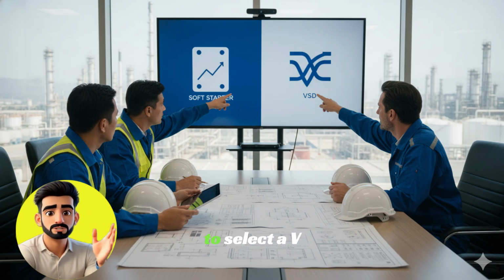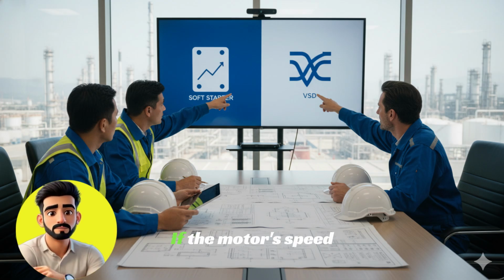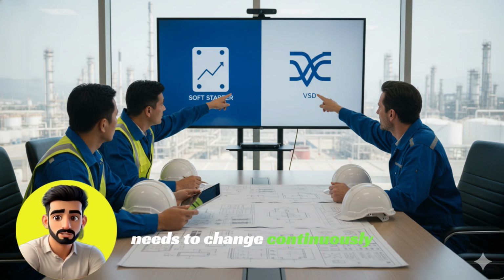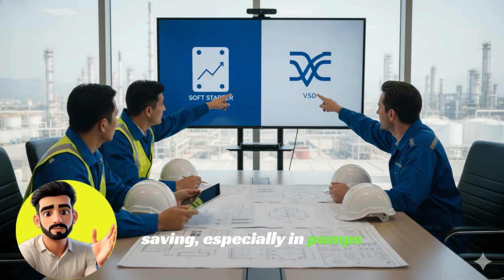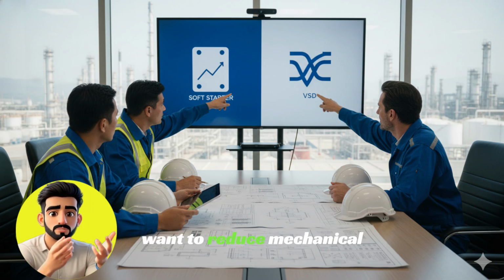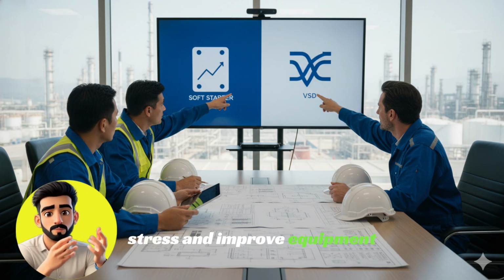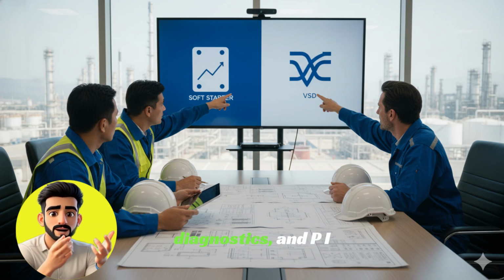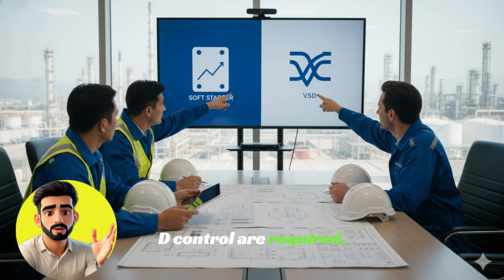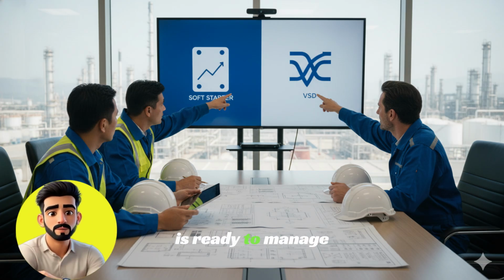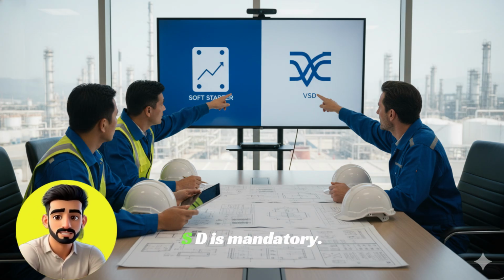Now let's see when to select a VSD. If the motor speed needs to change continuously according to the process, if there is a clear potential for energy saving, especially in pumps and fans, if you want to reduce mechanical stress and improve equipment life, if advanced protection, diagnostics, and PID control are required, and if the system is ready to manage harmonics, then a VSD is mandatory.